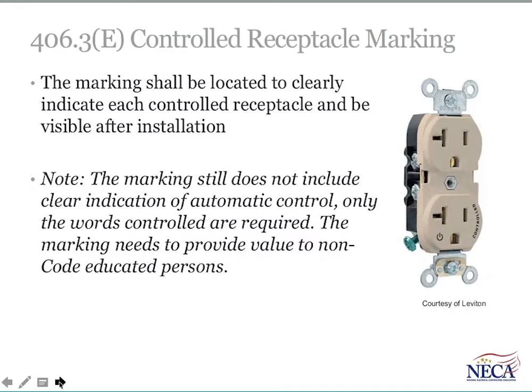Another change in Article 406, which covers receptacles, is a continued set of revisions dealing with the receptacles that are controlled by energy management systems. This is largely driven by the requirements in the ASHRAE 90 standard that requires a certain amount of receptacles to be automatically controlled by energy management.